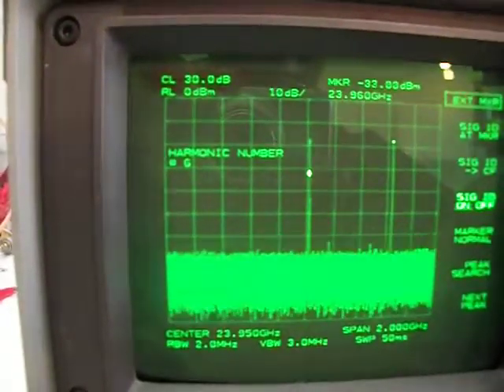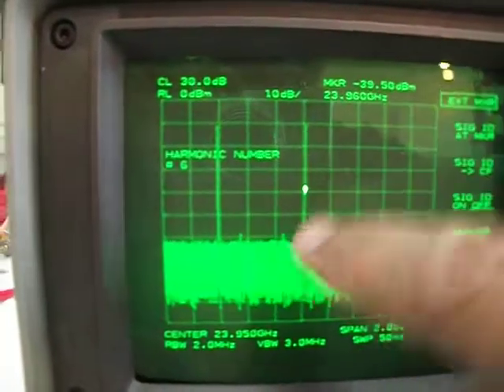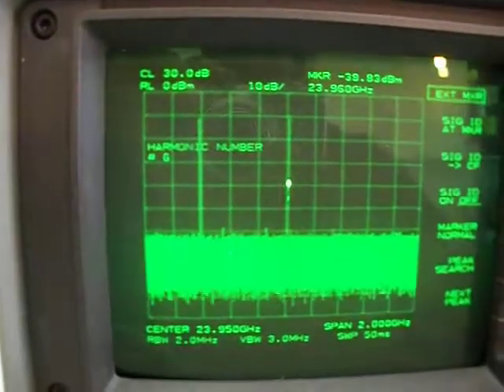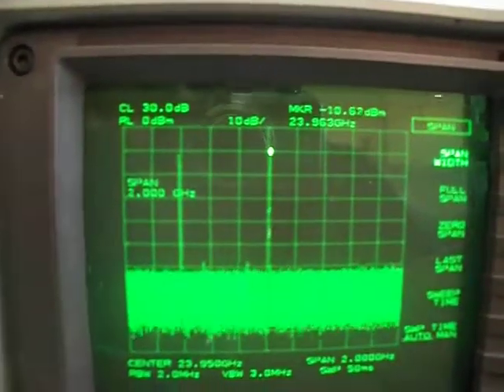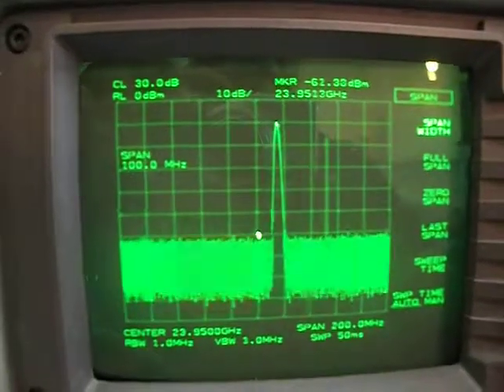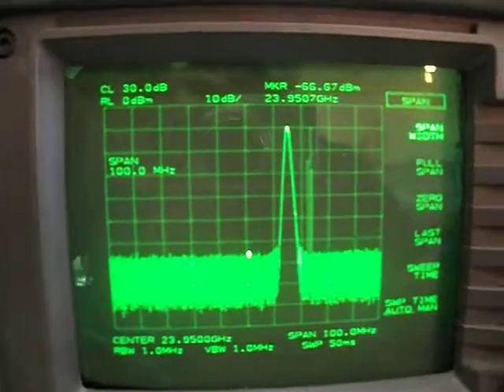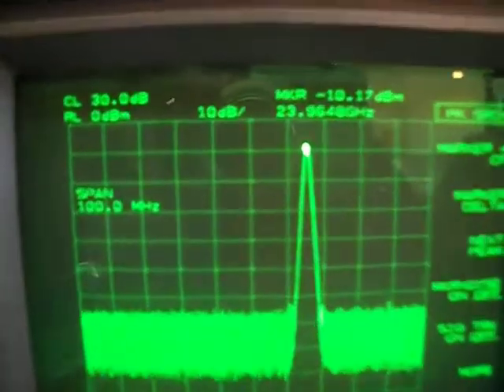Let's turn it off. The one in the middle is the correct frequency, which is 23.96 GHz. If we reduce the span, we'll be able to confirm that this is a 24 GHz signal.